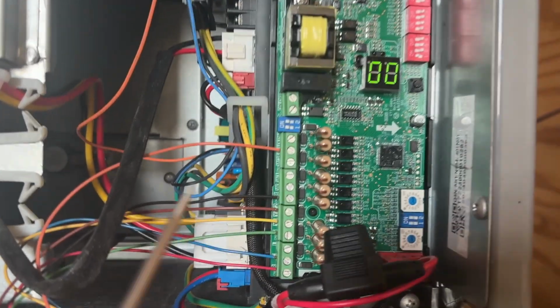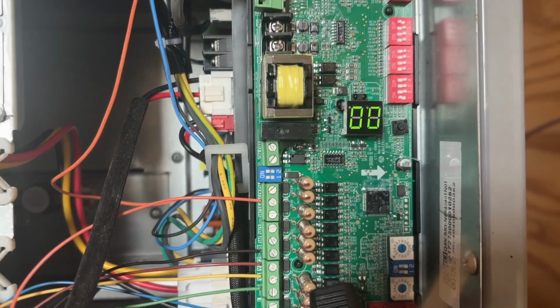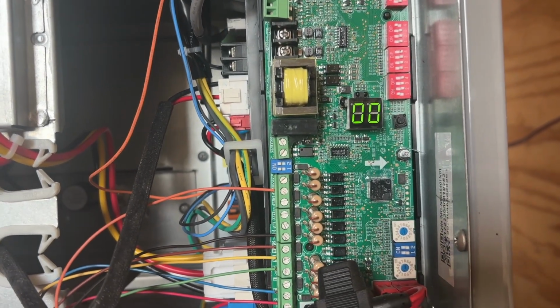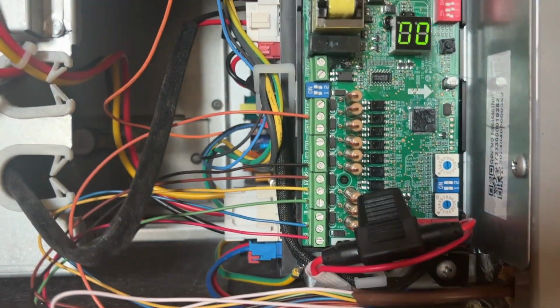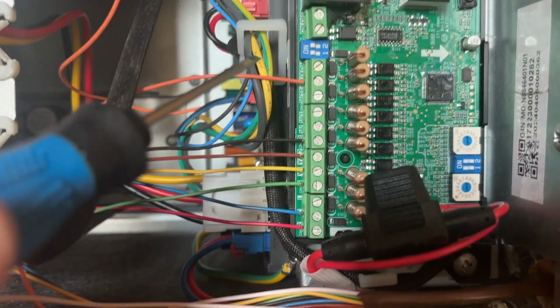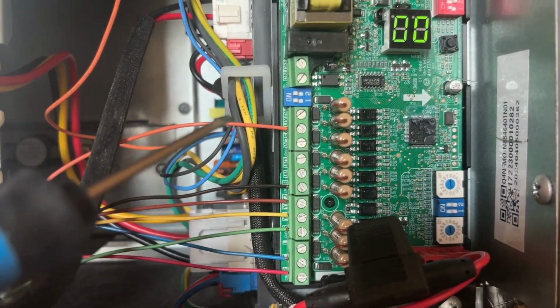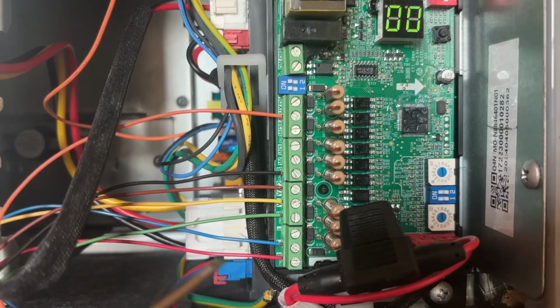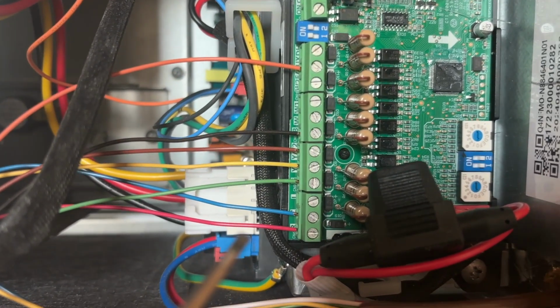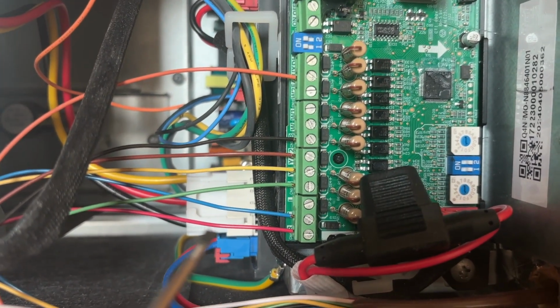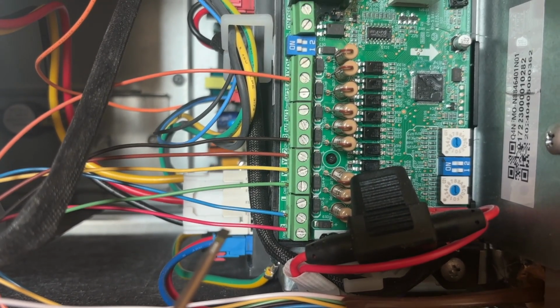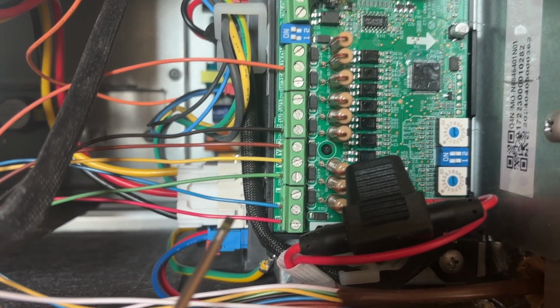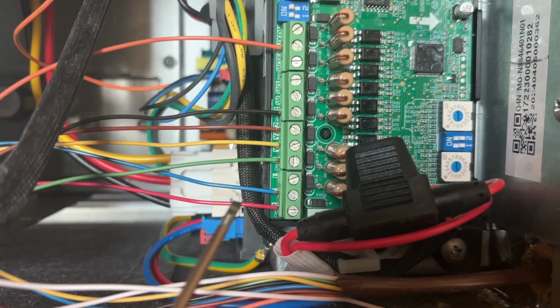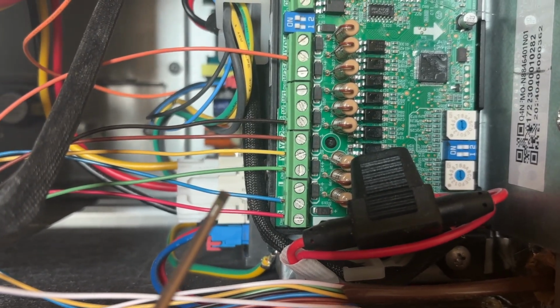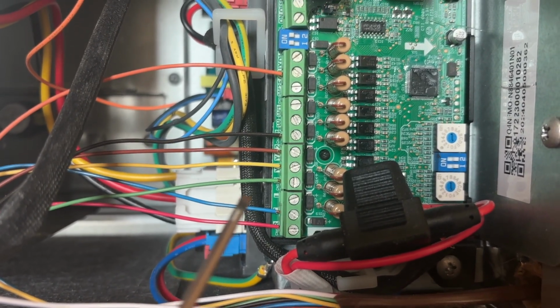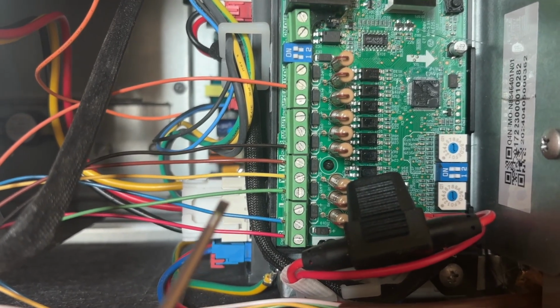With the unit off, you're going to see double zeros here. I do have power to this unit, so I'm going to be very careful on what I touch here. At the top of the 24-volt bar, you have the orange. At the bottom is the red. So let's talk about these. The red is the R, that's the power. So I'm getting power to the thermostat via the red wire. Blue is common. The C wire is basically the neutral wire to complete the circuit.